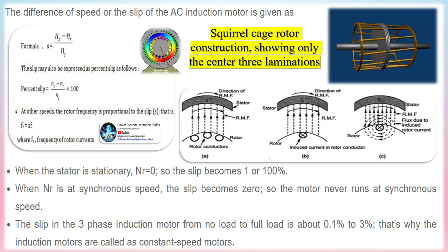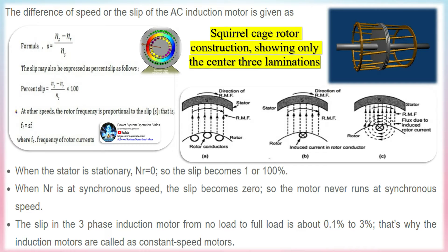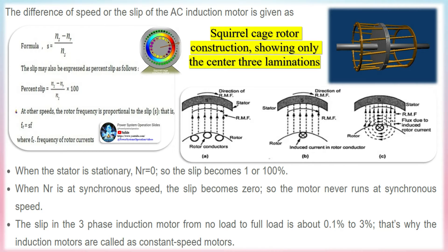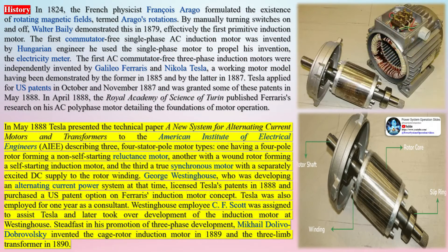If the rotor speed equals the stator field speed, no current will be induced in the rotor, because the reason for rotor rotation is the relative speed between the rotor and the stator magnetic fields. This difference between the stator and rotor field speeds is called slip. This is why a three-phase motor is called an asynchronous machine. The rotor speed nr must always be less than the stator field speed ns, and the difference between these two parameters depends on the load on the motor.